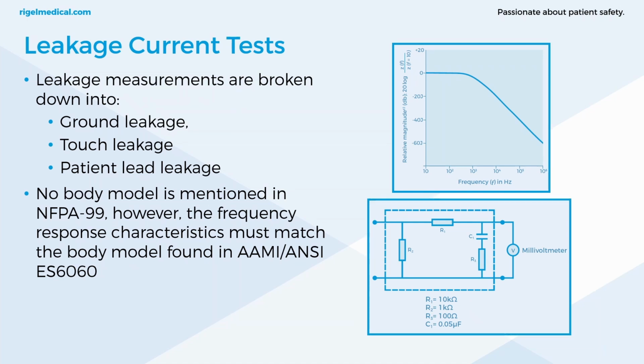Leakage current can be broken down into ground, touch and patient lead leakage. The terminologies are always changing and people call them by different things, not just between different countries, but even in the US, the terminologies can be used differently. So some people might call it touch leakage, but it also might be enclosure leakage. They might call it chassis leakage, but effectively it's the same measurement that's being made. These terminologies are always changing in the standards and the codes, and it depends when you came into the field what terminology you'll normally be using.